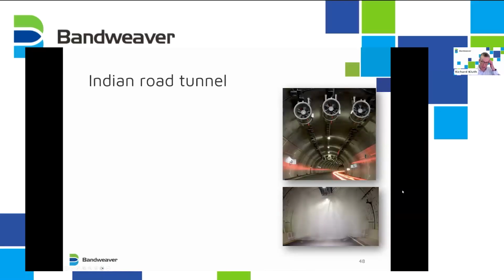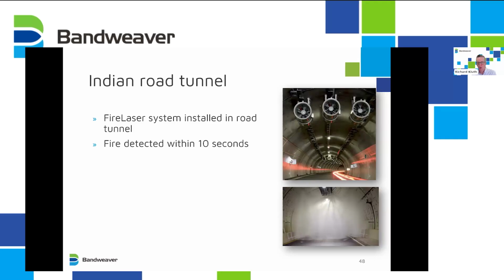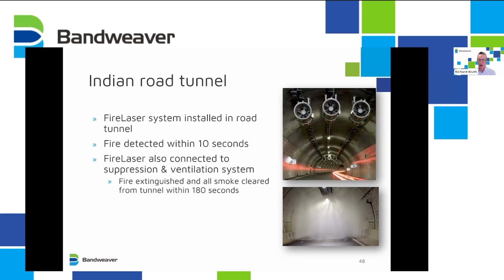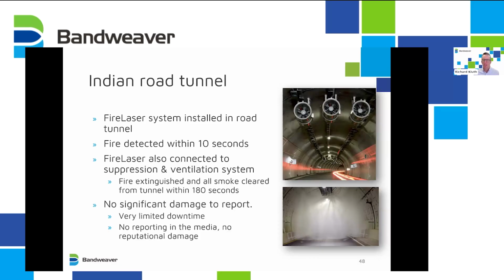Hopefully that gives you an example of the sensitivity. Our final example on road tunnels is an example in India where the FireLaser was installed, and it actually successfully detected a fire within 10 seconds. It was connected to the suppression and the ventilation systems. So the fire was extinguished and all smoke cleared from the tunnel within 180 seconds.